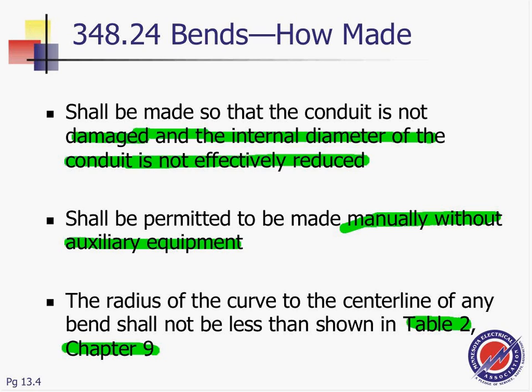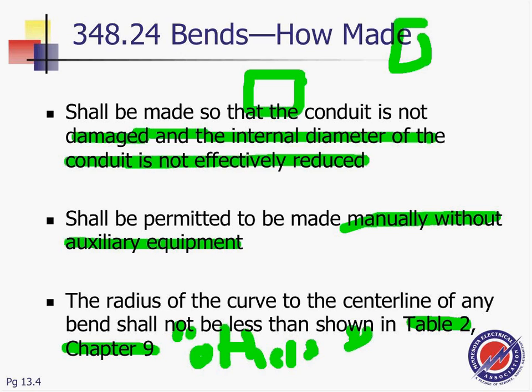So that's basically the bend table. If you go to Table 2, guys, there's the other bends, and under other bends you find the minimum radius you're supposed to bend this to. And so Joe might say, what the heck are you talking about, Chad? It's a 1/2 inch to 3/4, no big deal. But what if you are using a 4-inch? Remember that example we gave of a transformer to a panel? Now I'm using a big boy. I'm using a 4-inch to carry my conductor. That's a big conduit, guys.